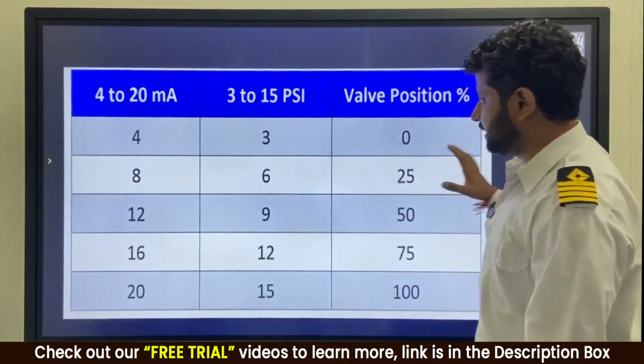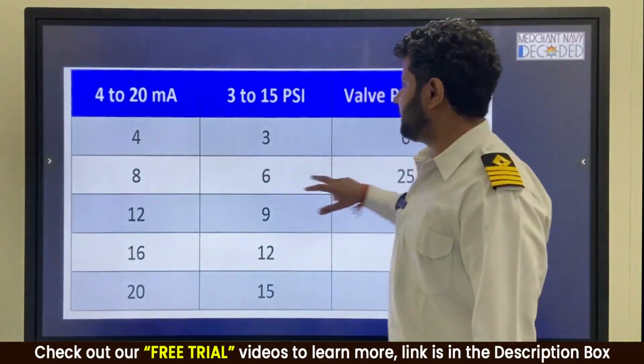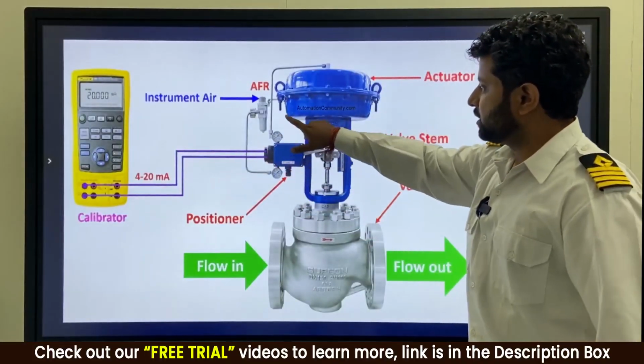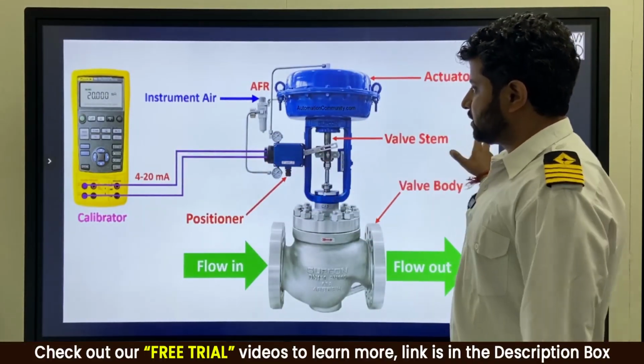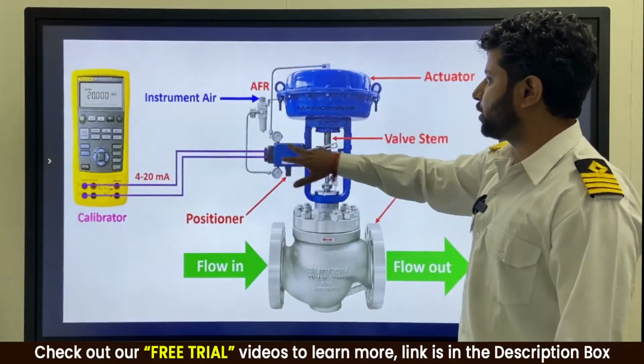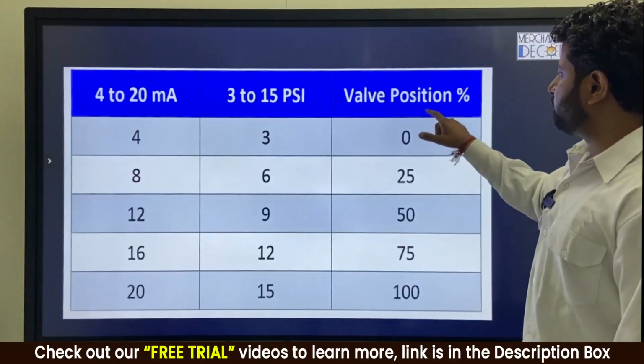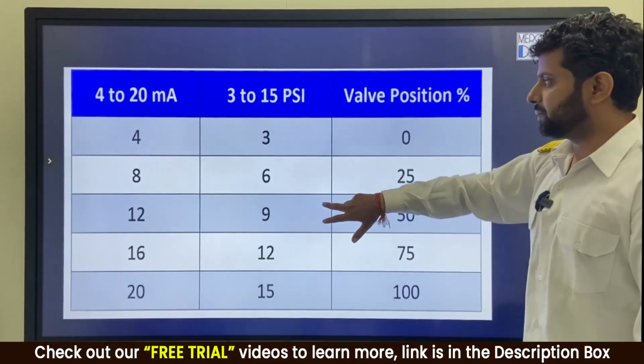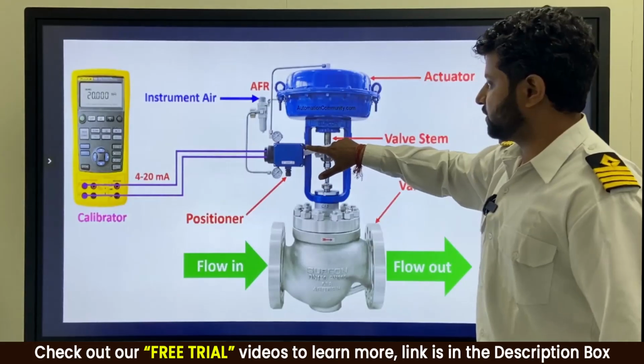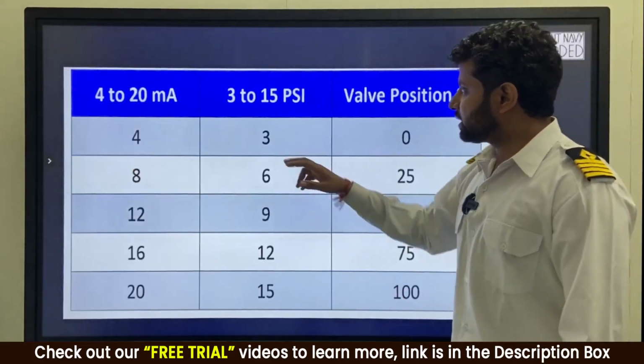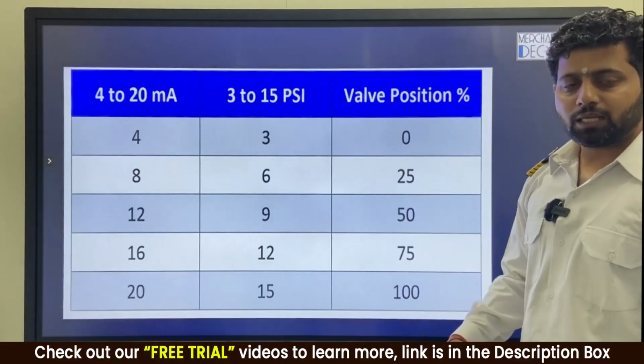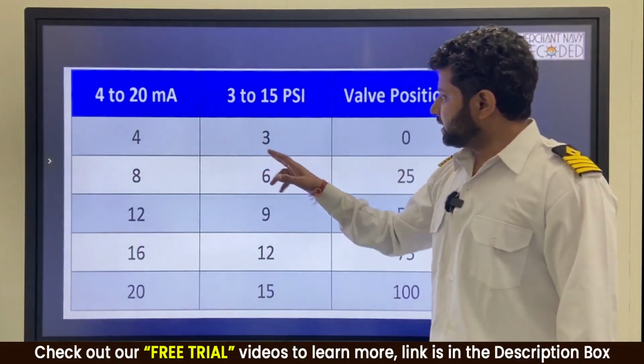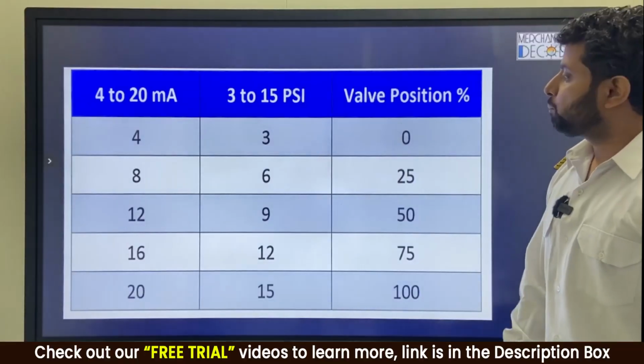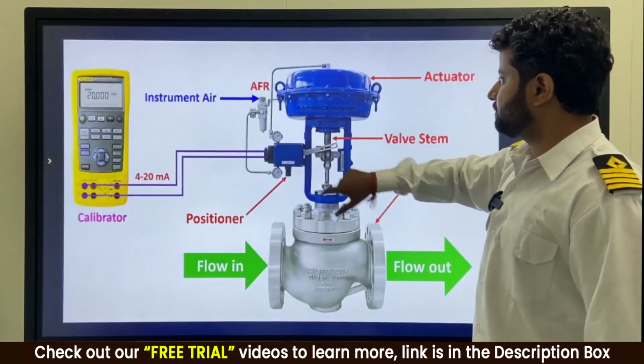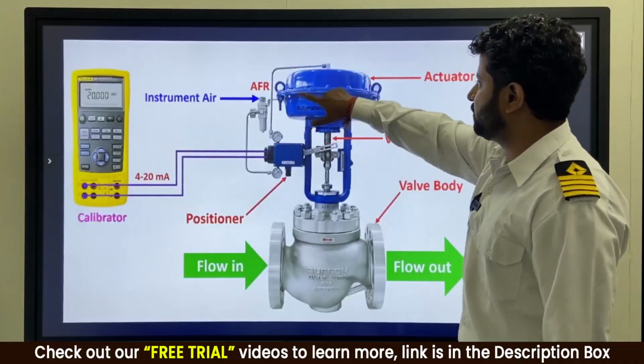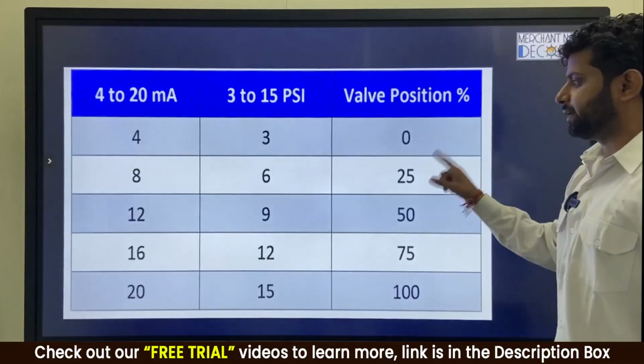So I just made a chart. When the signal is 4 milliamps over here, this 1.4 bar air waiting over here, the output air signal is coming only 3 psi, which is 0.2 bar. This 0.2 bar goes and the valve is 0% open, that is 100% shut. Copied. When the current becomes 8 milliamp over here, this output signal becomes 6 psi. 6 psi means 6 into 6.9 divided by 100, so this air will become around 0.4 bar, and when this 0.4 bar now will be acting on this diaphragm, it will slightly open the valve, it will be 25% open.